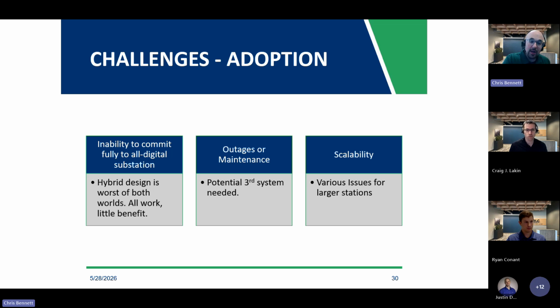The unfortunate part is that the hybrid design is the worst of both worlds. You're still running all your cables, you're experiencing the losses with copper, but you also need to set up the data mapping and the relays the same way as you would for a fully digital 61850 station. So you're using more time, more resources, which makes it somewhat not beneficial depending on your specific need.